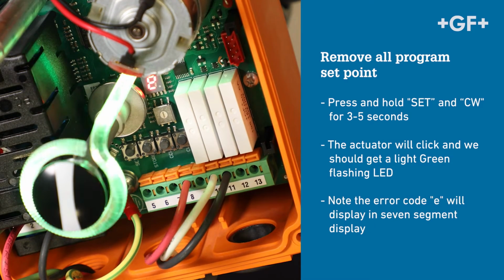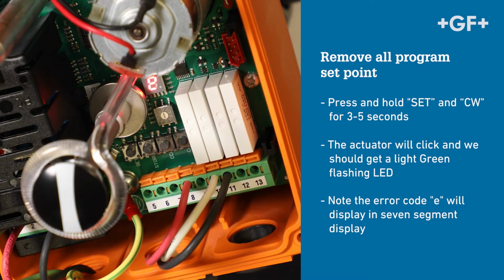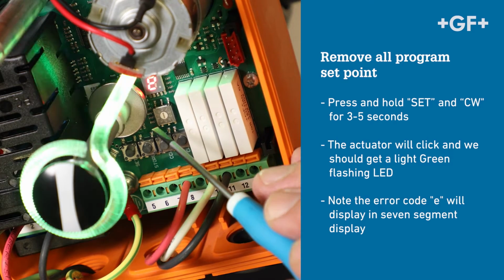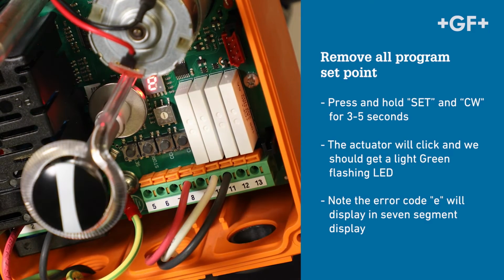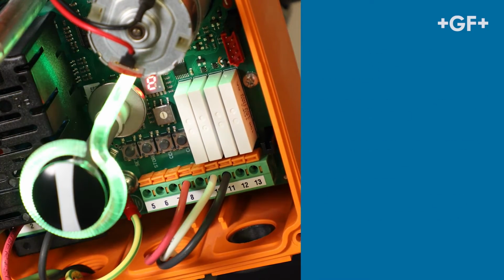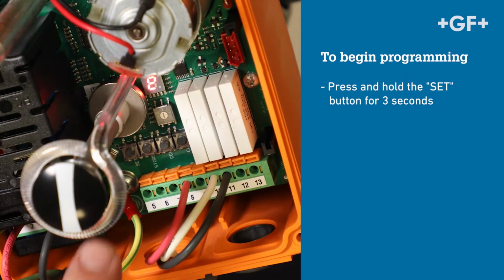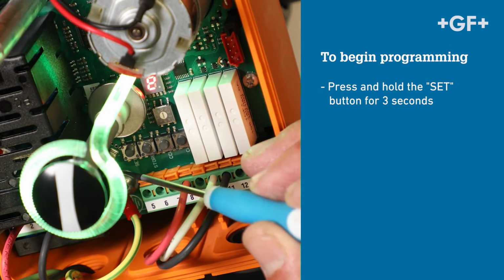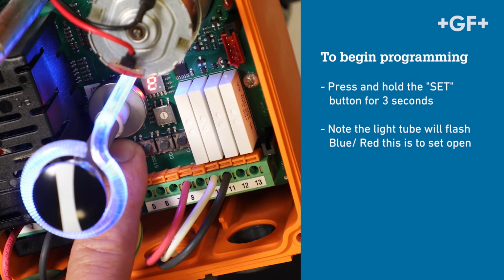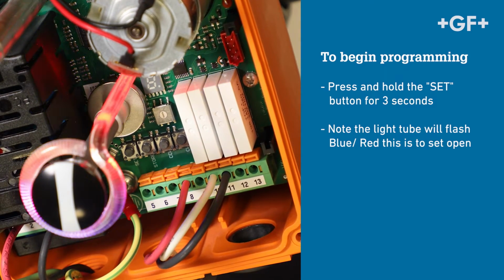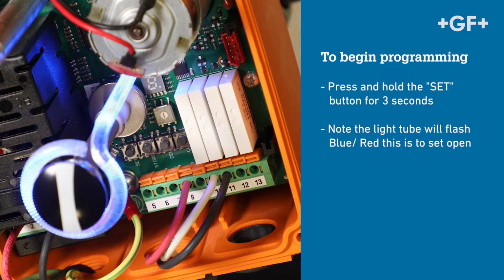Note the E in the 7-segment display. This is indicating an error in position. Now we're ready to program the end stops. To begin, press and hold the Set button for 3 seconds. Note, the LED light tube is flashing blue and red. This is to program the open position.